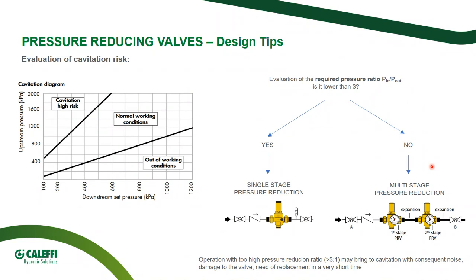Another very important tip, consider the required pressure ratio, so the ratio between inlet pressure and outlet pressure. The limit in order to prevent cavitation issues is 3. So this question is very important. Is the ratio lower than 3? In case the answer is yes, no problem, we can go with a single stage pressure reduction. But in case it is no, so the ratio is higher than 3, we warmly recommend to consider a multi-stage type pressure reduction, so with a first stage PRV and a second stage PRV.